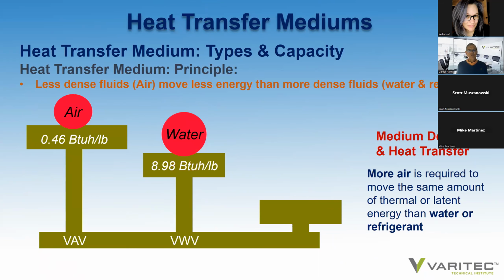What about water as a heat transfer medium? Water is much more dense than air. Water can hold 8.98 BTUs per pound of water. Consequently, you can remove 3,300 times more energy using water as a heat transfer medium than air, meaning that it requires less pumping horsepower to move the same amount of energy from a building than the fan horsepower an all-air system would require. This is where your energy efficiency comes in for chilled beam systems and passive radiant cooling and heating, because we actually use water as the sensible heat transfer medium local to each zone, not air.